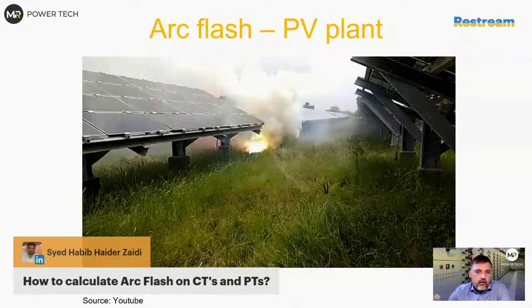But if you would like to do a calculation on CTs and PTs in your medium voltage switchgear, you still can do it. So this will be just like everything else. But I will stop on the primary side. I will not go to the other one. Doesn't make sense. What I will generally do is calculate it as for all the systems. So this will be like one feeder. You add it to the main.